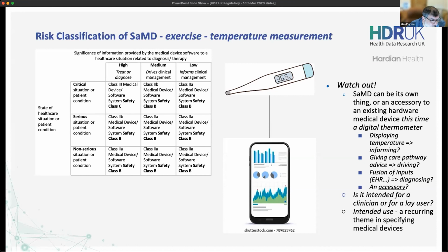Okay, how come there are mental health class 1 devices which take questionnaire measures and present these scores to users, for example? I think it's the same reason. The MDD, so the European Union, if they're deployed in the EU, they're under MDR Article 120, which says if you've got something under the old class 1 regime by the 25th of May 2021, you've got some time period in which to upgrade it to a class 2. You can keep it as a class 1 as long as there's no significant change, which I think Candy will come on to, what significant change means.